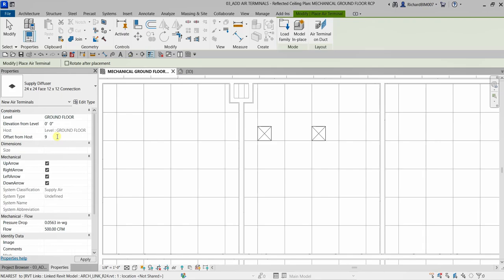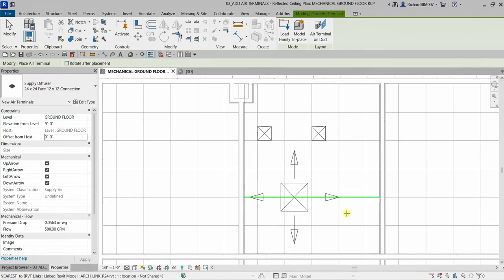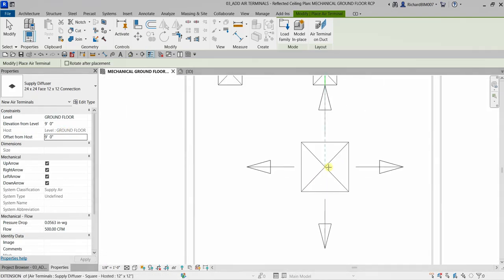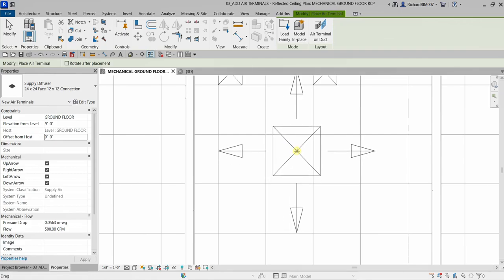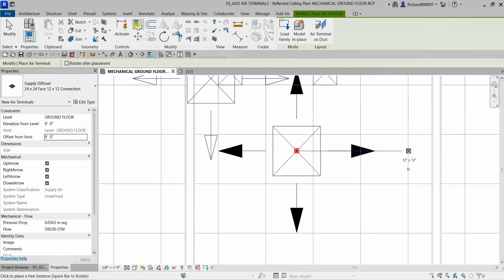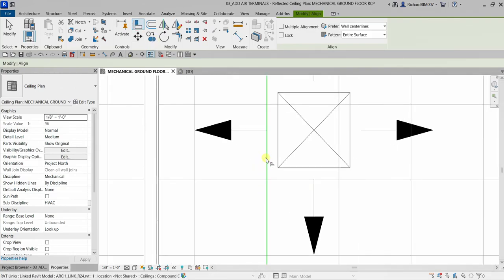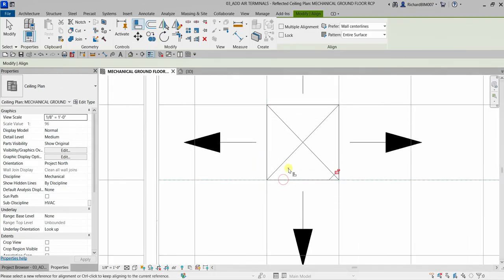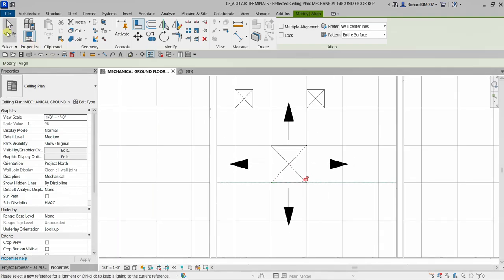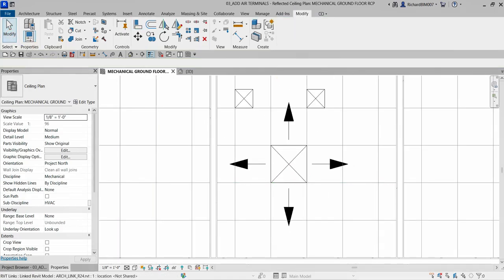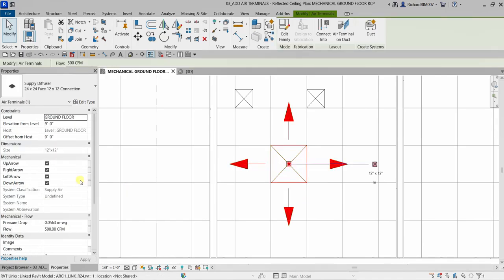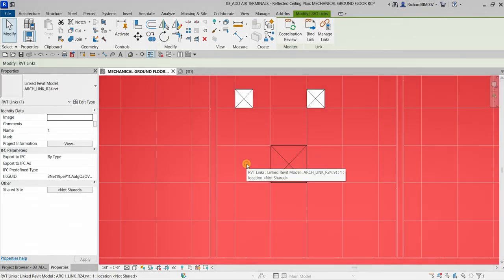I'll change the offset height to 9 feet - type 9, Enter. Once you do that, you'll be able to see the terminal in your ceiling plan. I place it in position and use the Align tool to align both sides. Then I select the air terminal, and there's an option to hide the directional arrows of the air terminal.